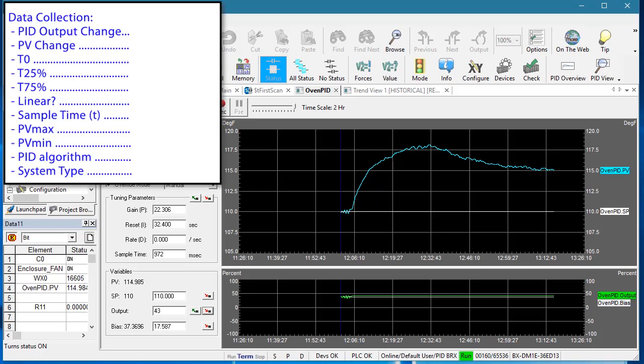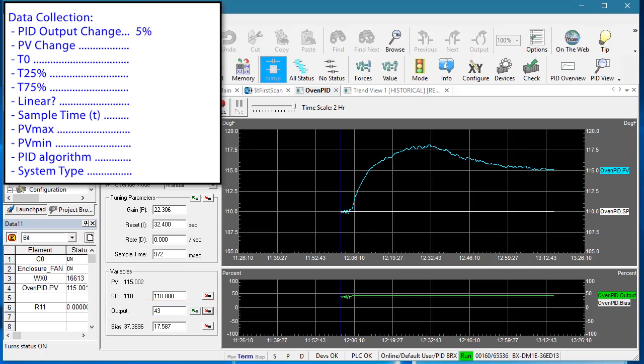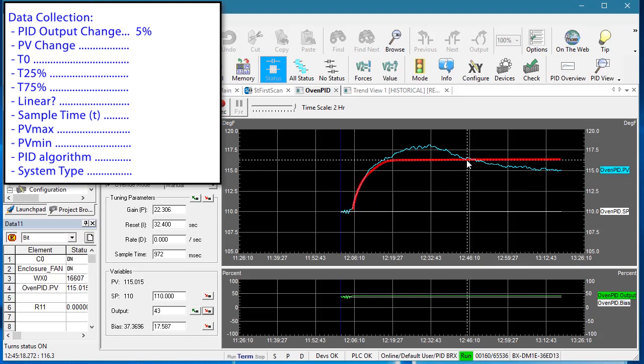The PID output change – we bumped our output 5 percent. The process variable change – now the highs and lows that you see here are being caused by my office air conditioner turning on and off. So we have to use our imagination and say it really looks like this, which is a 6.5 degree change.